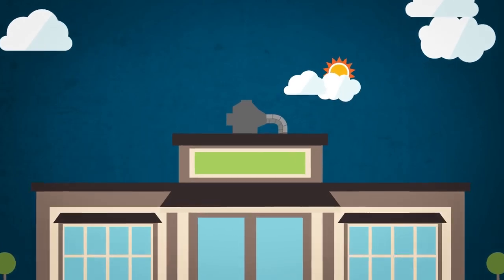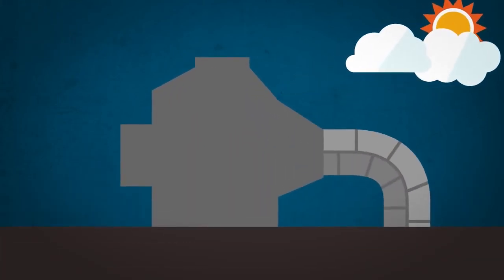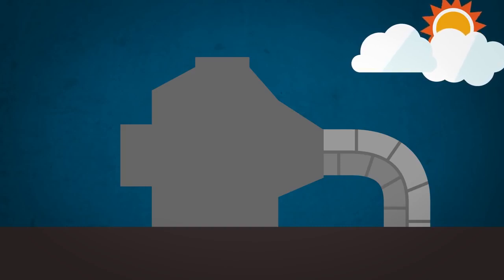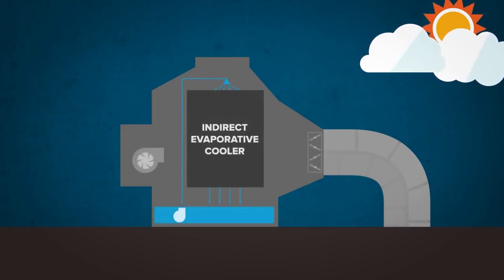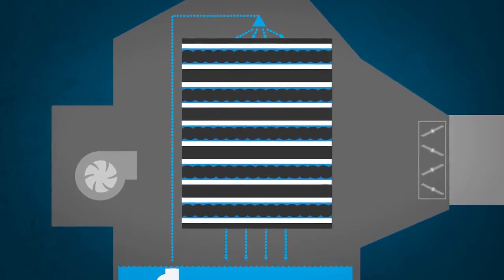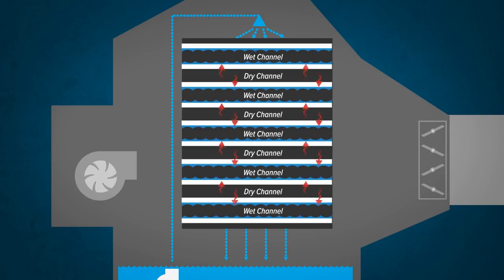Climate Wizard is a standalone technology that delivers 100% cooled ventilation air. It uses significantly less electricity than a standard rooftop air conditioner and adds no humidity to the building. It does this by using an indirect evaporative cooling process. Let's explain that further. The heat exchanger in the Climate Wizard is made up of a series of alternating wet channels and dry channels, which are designed to transfer heat between them.